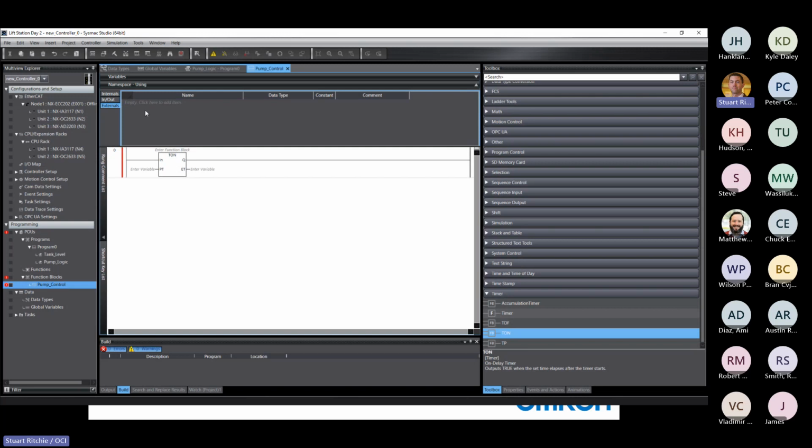If it's just for your project and you have way too many in/out variables and you could get away with moving some of those to externals, sure, that would be a good use case. The function block we're going to create is just a basic start, stop, pump control, but with something we didn't do in the first class: adding run feedback and a fail to start timer. The first thing we're going to do, you can create the variables as you go, or you can create them and then program your code.